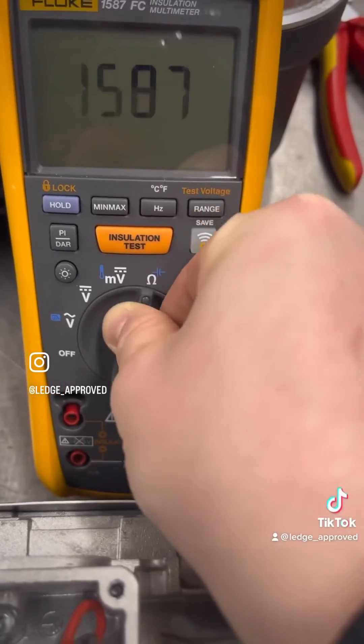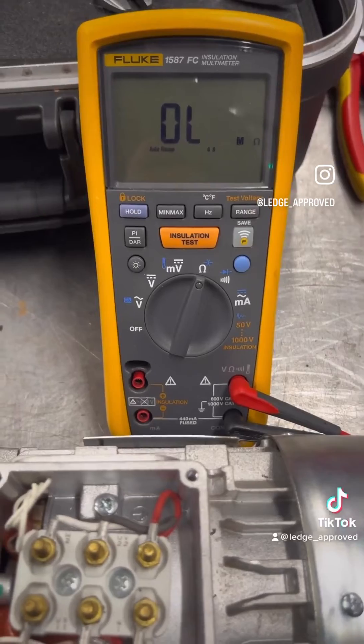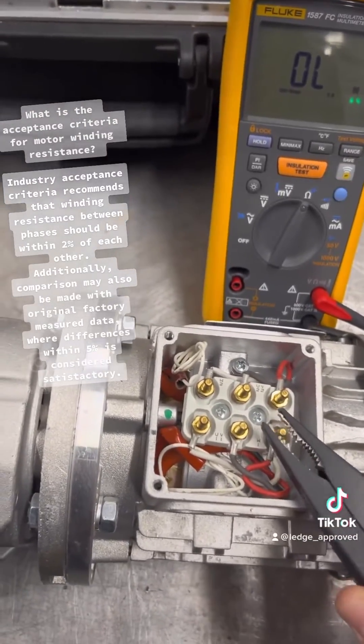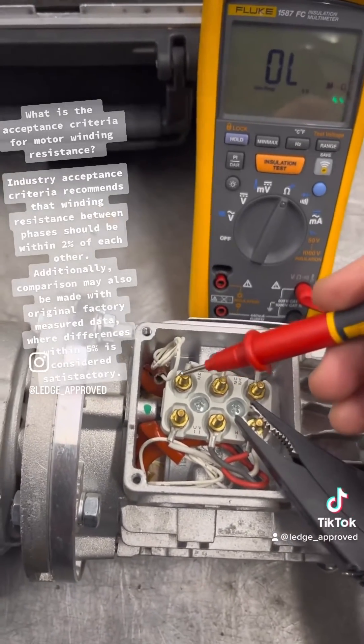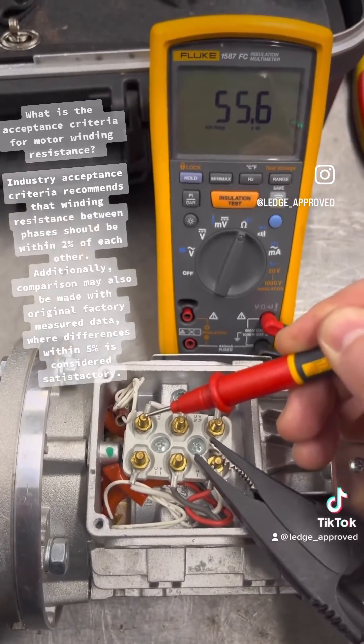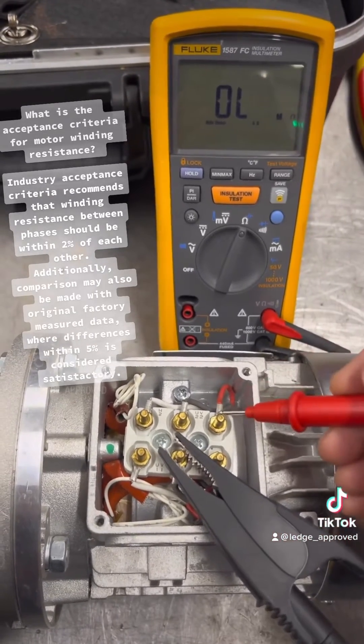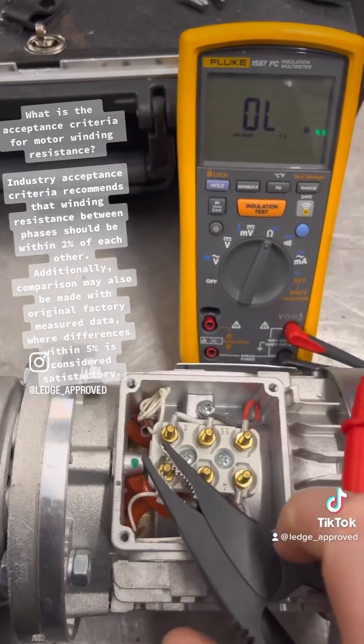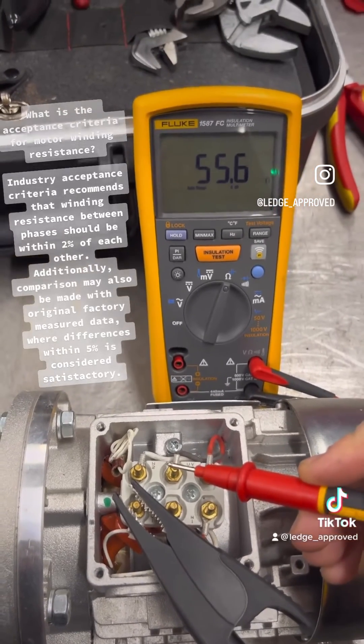Now we're going to be doing the resistance across the three windings. Now in the industrial setting, we're looking for normally about 1% — we want no more than 1% change across the three windings, so balanced across them. So as long as it's balanced, we're good to go. Now that's ledge approved.